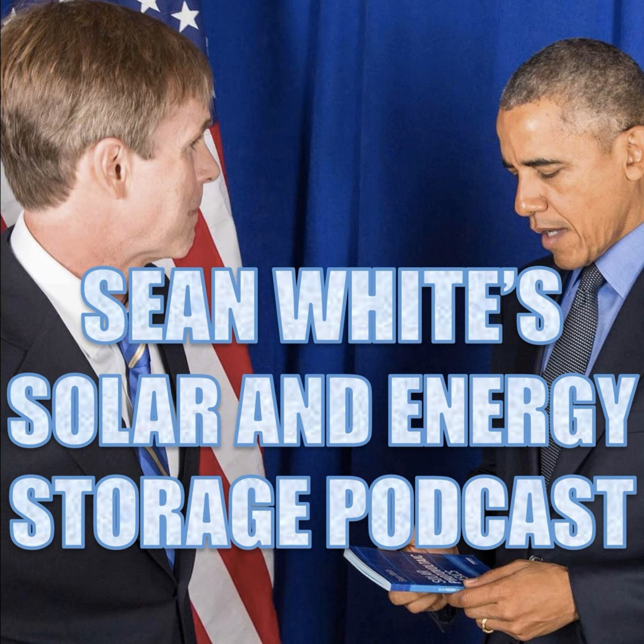So your VA is the same as your watts. And so we've got a 2000 watt inverter. And for 30 minutes, it can give you 2,500 watts. And for 5 seconds, it can give you 4,300 watts. And for 1/10 of a second, that's 100 milliseconds, it can kick 4,600 watts at you. So that's just going to show you that this 2,000 watt inverter that we would describe as a 2,000 watt inverter can give you up to 4,600 watts, and that's for these different levels of surges.